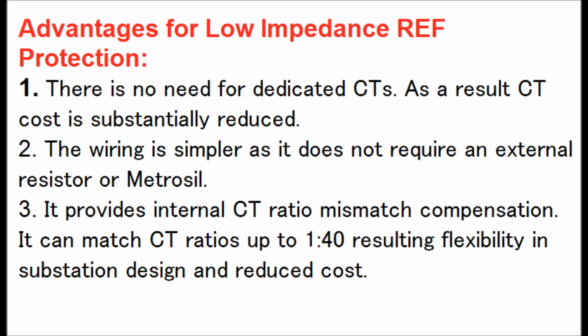That is, all the CT mismatch is calculated inside the relay by providing a factor K, which is equal to the neutral CT ratio by the phase CT ratio or bushing CT ratio, which will calculate all the CT mismatch, and it will take the primary value or convert the CT current to the same base value.